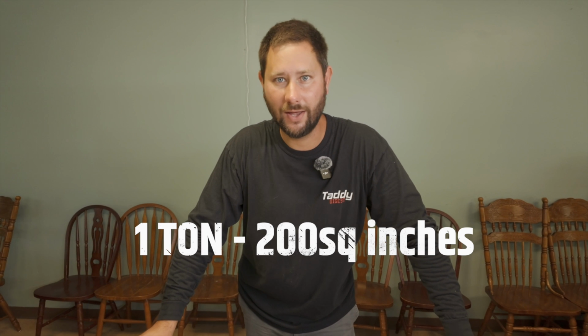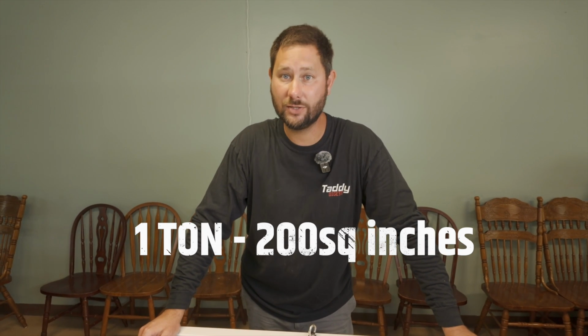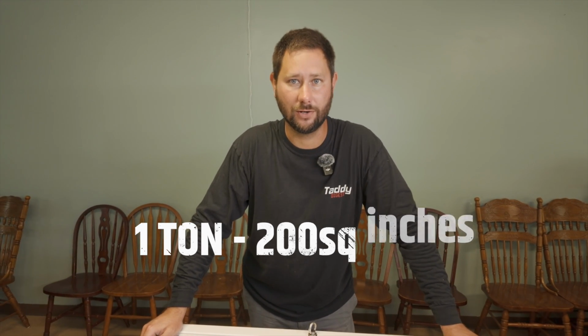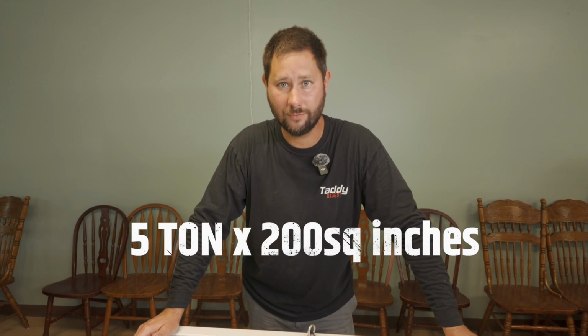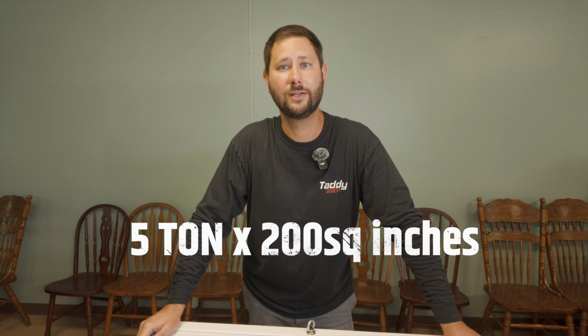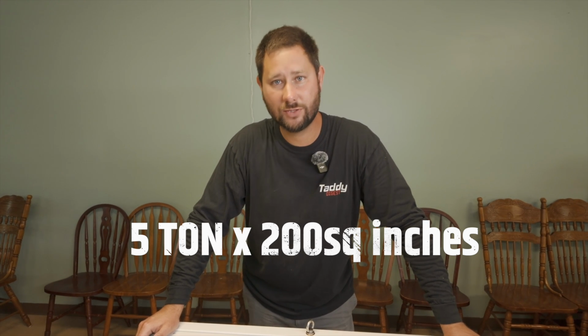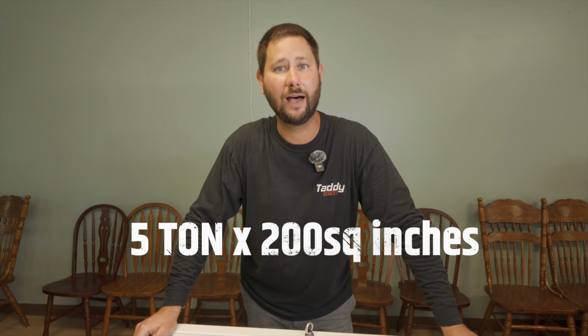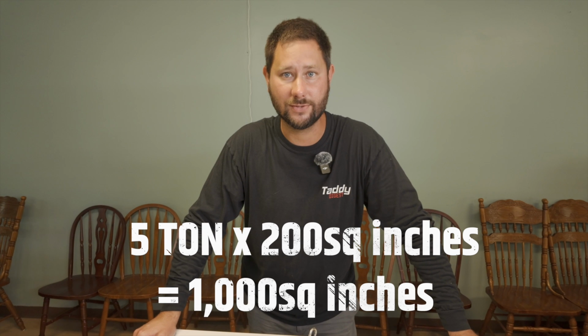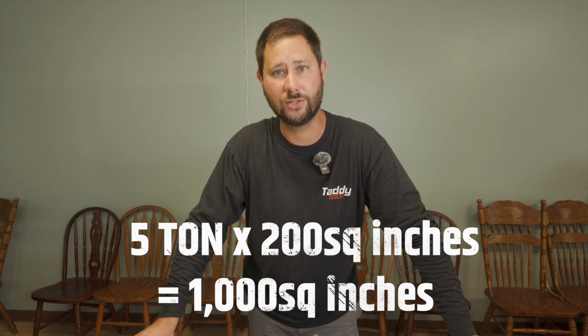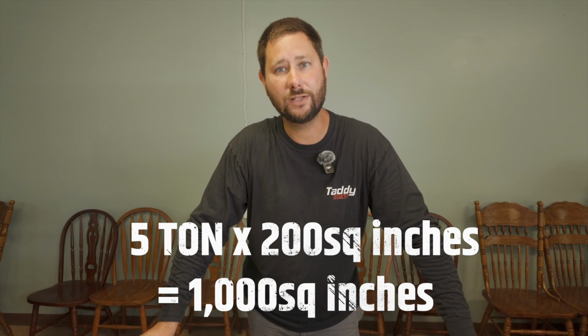Now to figure out what size return grill you need, we got to do a little math. For every 1 ton of air conditioning, we need 200 square inches of return. So what we're going to do is take the 5-ton that we have and multiply it by 200. So 5 times 2 is 10. So 5 times 200 is 1,000 square inches.